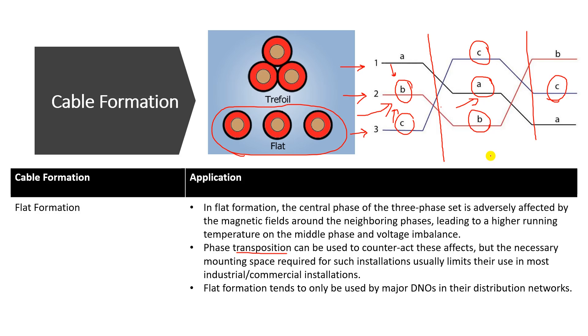Since all cables in the flat formation are separate, phase transposition helps reduce the imbalance effect. However, the flat formation requires more space for installation, so it is very limited in low-voltage industrial and commercial installations — those typically use the trefoil formation, or more commonly, a single multi-core cable instead of three separate cables. The flat formation is mainly used by distribution network operators (DNOs) in their distribution networks. The next lesson will cover the derating factor in cables due to formation.